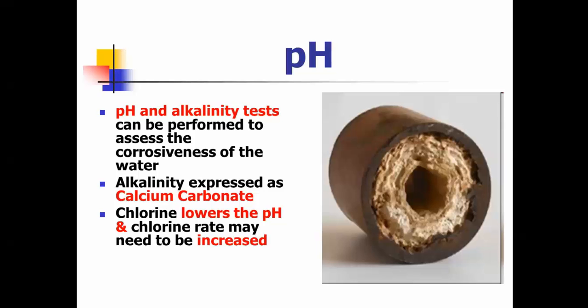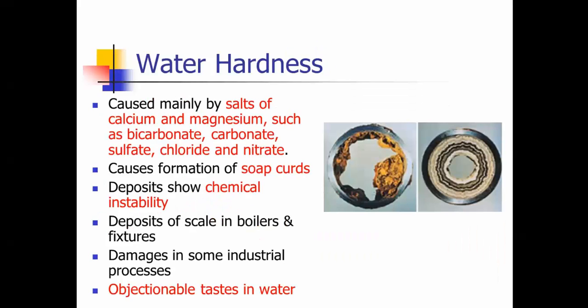This is a picture of a cutaway of a piece of pipe that has scaled. It's expressed as calcium carbonate, and chlorine also lowers the pH in the water system. It makes it more aggressive. So if you have that in the line, if you are adjusting for scaling in your line, you may need to adjust your chlorine use and increase it more so you get a good kill rate.